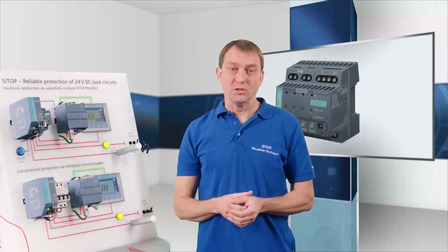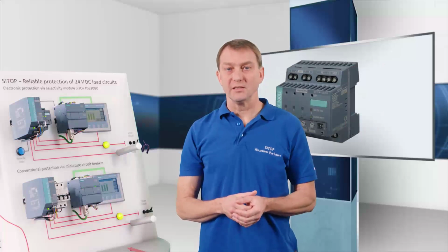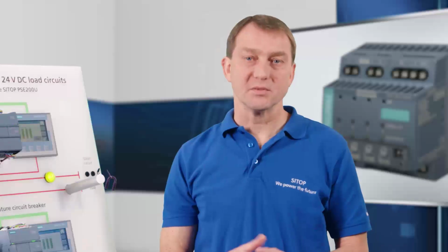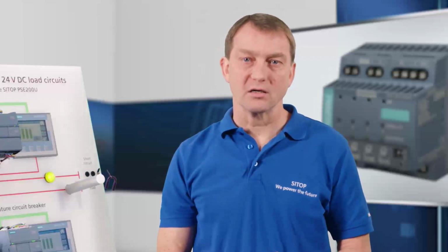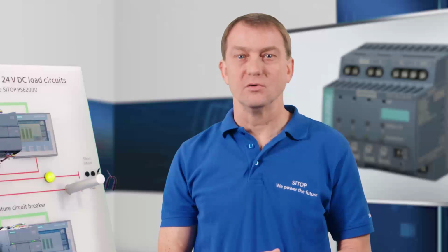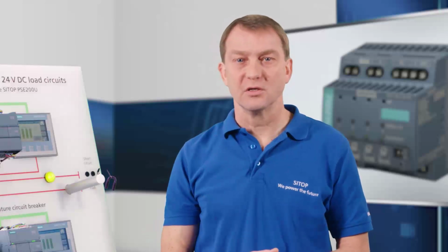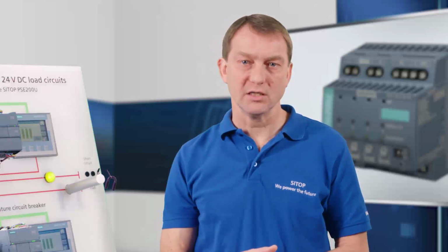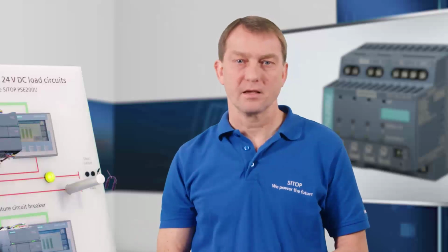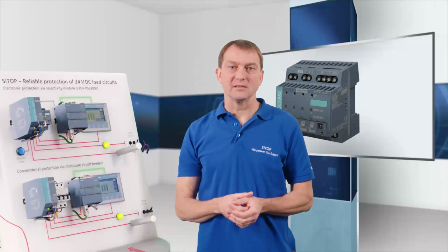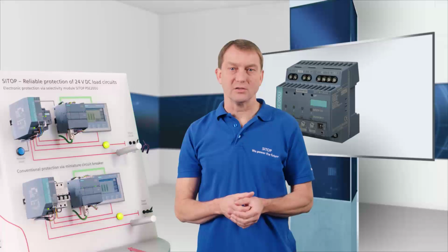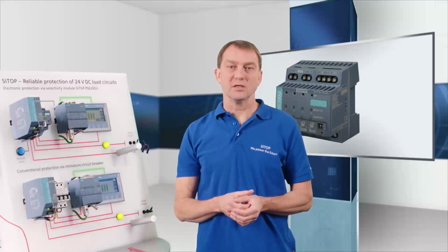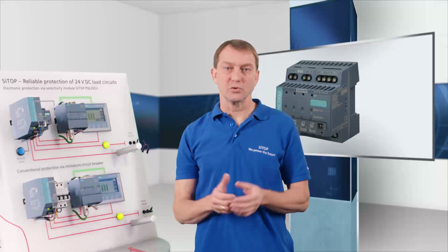The selectivity module is also available for US standard NEC Class 2. Even in the event of a fault, each output is limited to 100 watts, and only loads that have approval for use with NEC Class 2 may be supplied. In the USA, this UL standard greatly facilitates acceptance and wiring and enables cheaper products to be used in the control circuit.